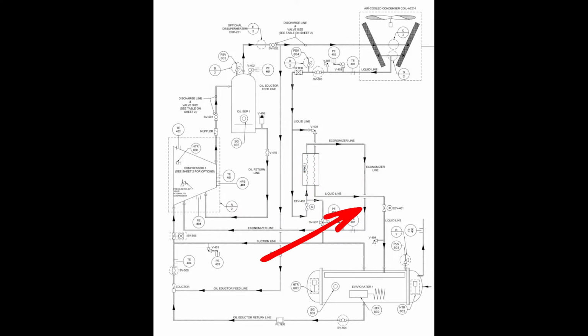That deeper subcooling then processes back over to the evaporator through our primary evaporator metering device. And I'm saying this wrong. This comes over here. So this line here comes into the braze plate, comes out, and then we have our evaporator metering device, which is an EXV after the economizer.